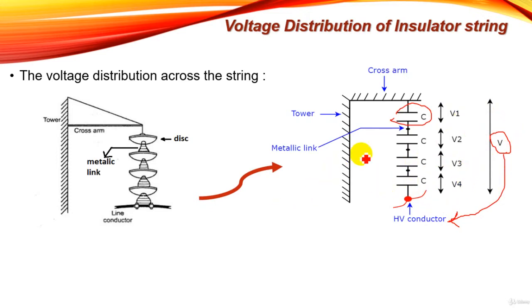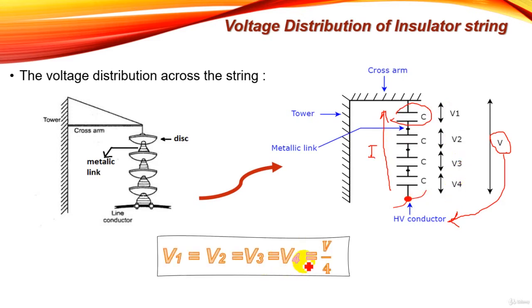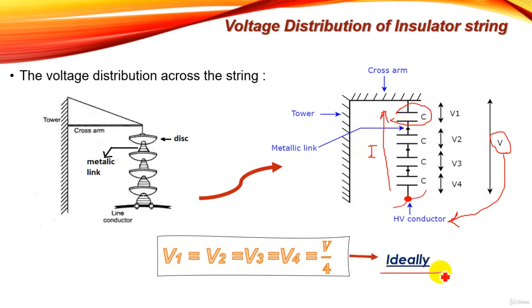In the ideal case, all capacitors have the same value and the same current flows through each capacitor. From these two facts we can deduce that V1 equals V2 equals V3 equals V4, and each voltage equals the total voltage V divided by 4, where 4 is the number of units. This is the ideal voltage distribution, but unfortunately this ideal case does not happen in a real insulator string.